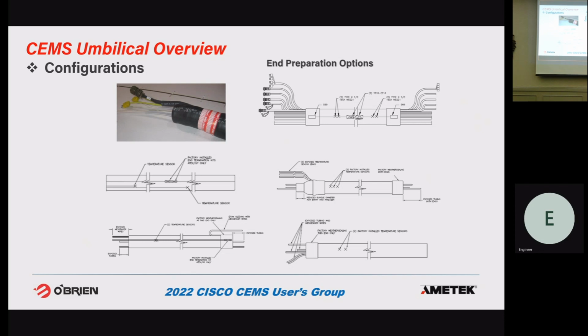I'm also showing here, all tracer has a maximum circuit length depending on the watt density and supply voltage. When you reach that length, you can't go further. So what we can do is essentially double the tracer - in the factory we put end terminations inside the bundle to double the circuit length. It's two independent circuits but one complete tubing bundle. You have to bring power to both ends, so we can put a cable in there to bring power to the other end. If it needs temperature control, you have to control them separately, but at least you'd have a single 500-foot tubing bundle instead of splicing two bundles in the field.